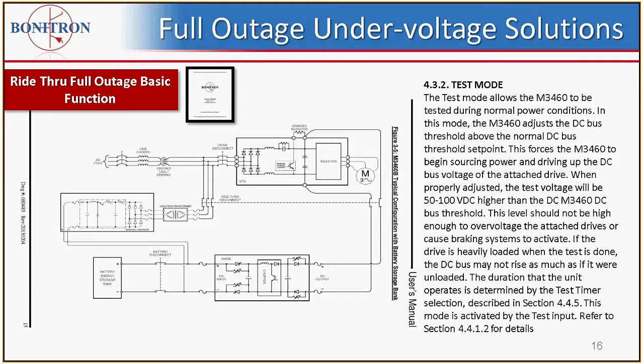The differences between the SAG ride-through booster and the M3460B, or what we call the battery boosters, is just that the Bs are rated for a higher duty. They are standard 4 minutes, but we can derate them up to, I've done 4 hours before. So anything between would be the battery boosters. But if you're above 5 seconds, we would recommend battery energy storage, only because of the economical issues with UltraCaps.